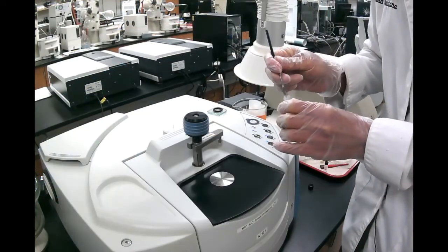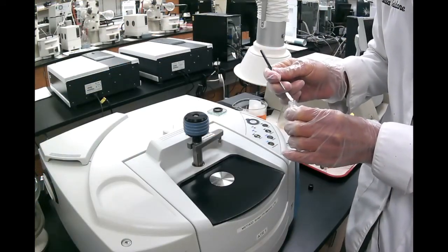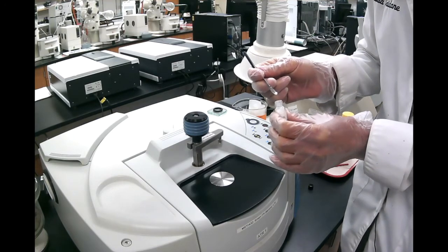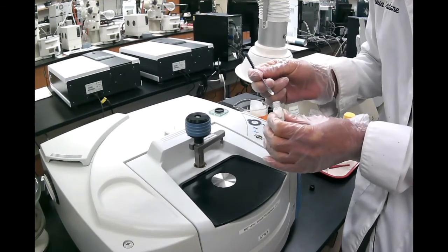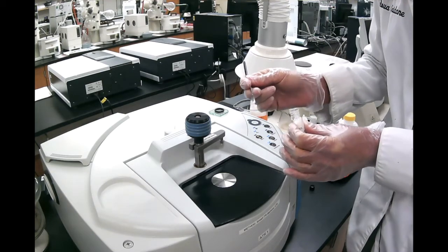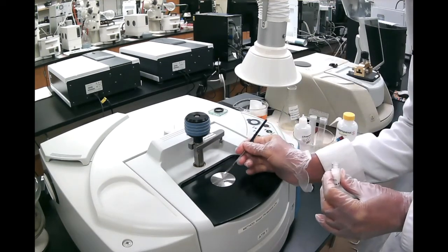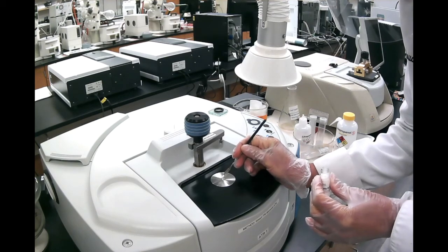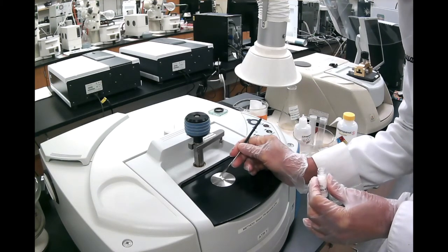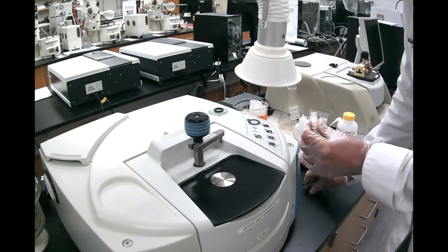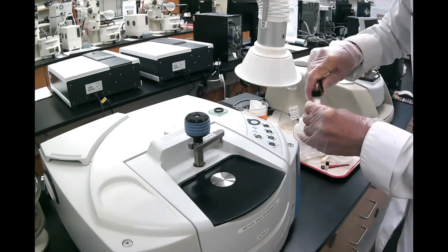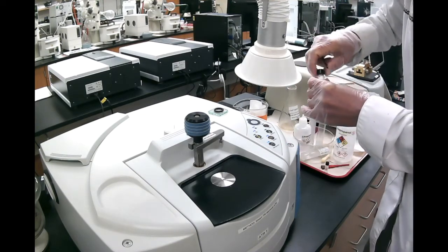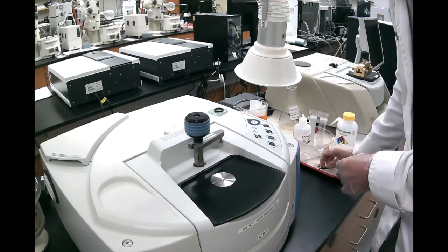So how do we put a solid sample? First of all, make sure its crystal is a fine powder. You definitely need a fine powder, and all you need to do is put it on the little diamond right there. Just put a little bit of it. Don't overdo it. And then we need to compact the sample. So how do you do it?